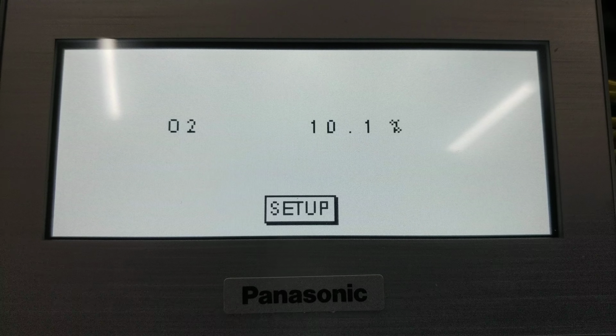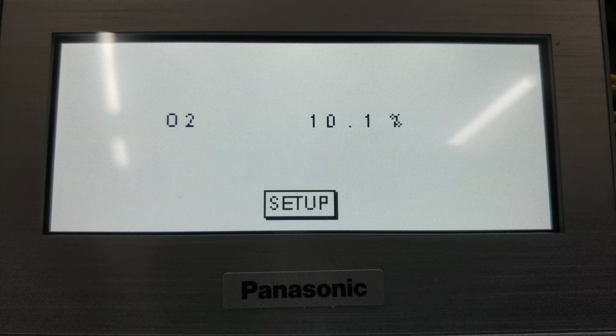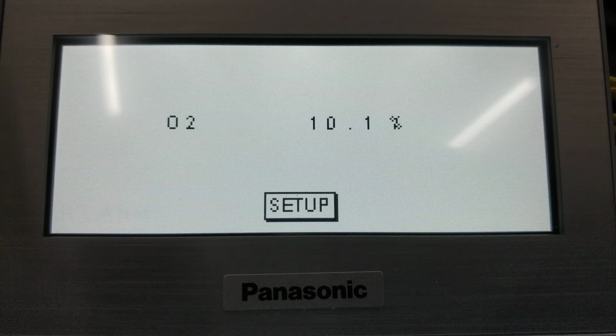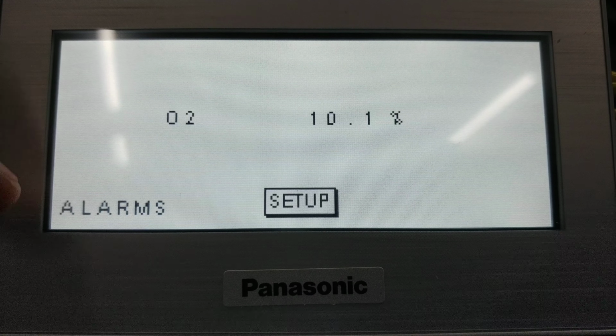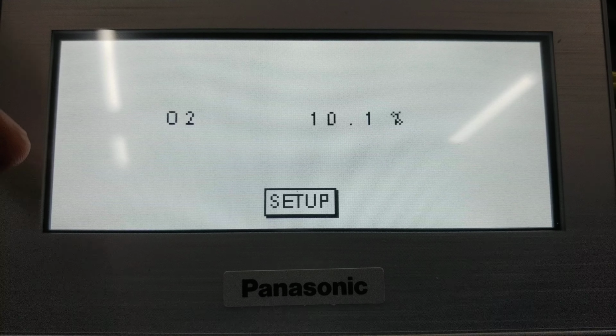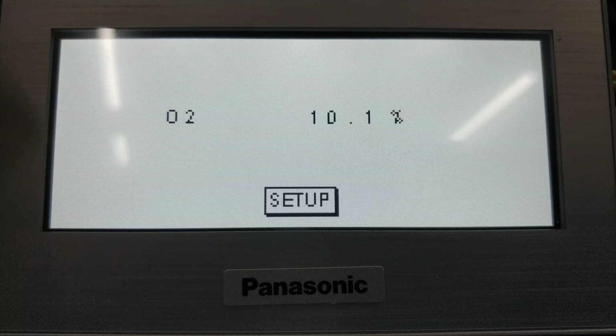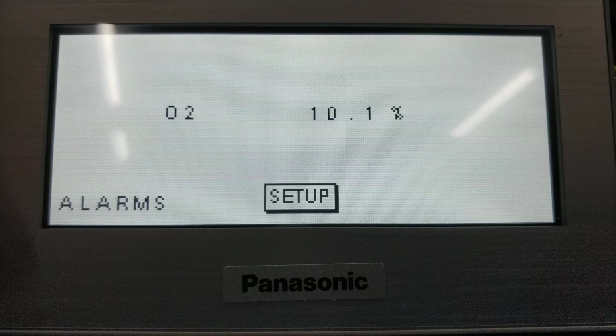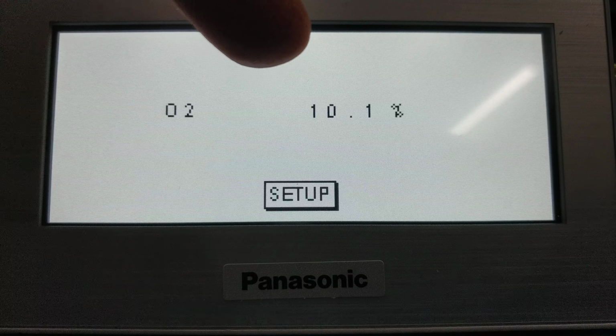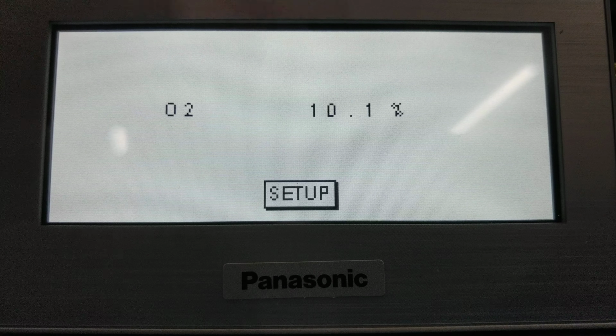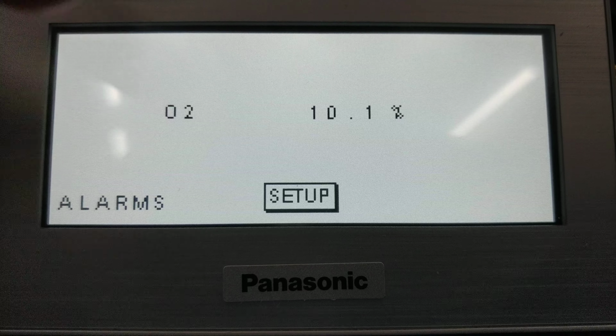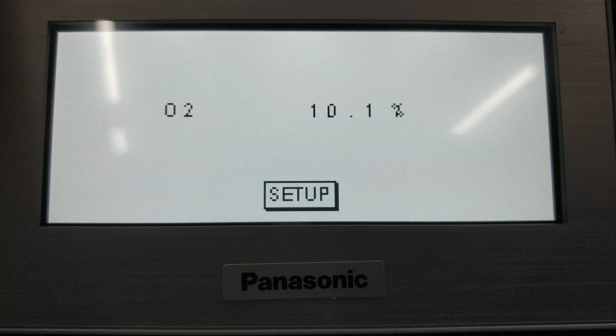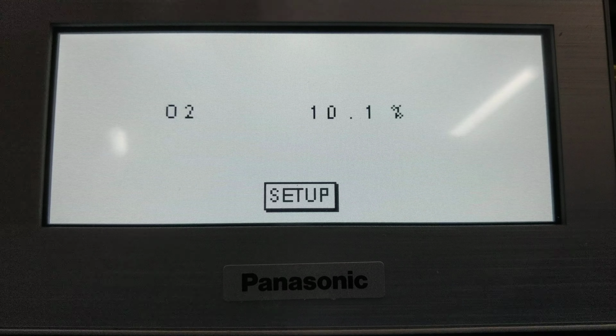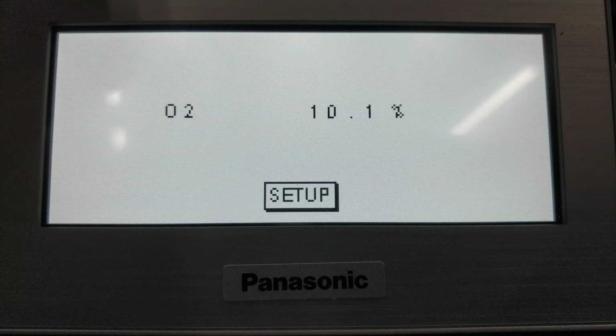Alright, in this video I'm going to show you how to do a span calibration and how to change the alarm set point. So as you see right now, we're getting an alarm. This is a gas alarm because our gas alarm is set to trigger at 2%. And as you can see, we're simulating a 10% reading, sample reading right now. So you're going to get this gas alarm regardless. That's fine. We're just going to go ahead with a calibration right now, a span calibration.